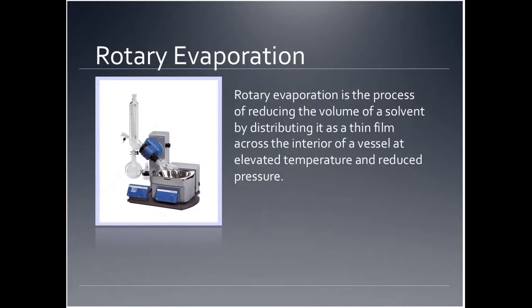Rotary evaporators, or rotovaps as they are usually called in the lab, are important pieces of equipment used to promote the rapid removal of excess solvent from less volatile samples or samples with high boiling points like water. In many laboratory processes, large amounts of chemicals are used to perform certain experiments, but analytical instrumentation only requires a small amount for testing. A scientist would use a rotovap to evaporate off the excess solvent, leaving the small amount needed for testing — for example, taking a large sample of salt water and gently removing all the excess water to expose the salt crystals. We have two rotary evaporators in our lab.